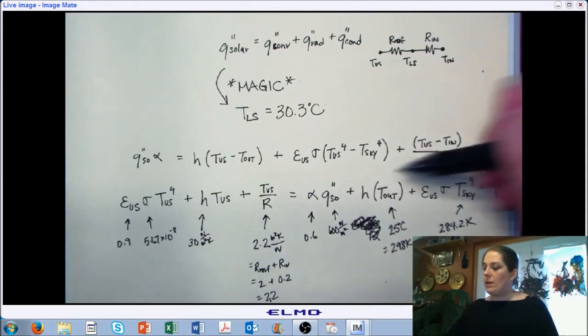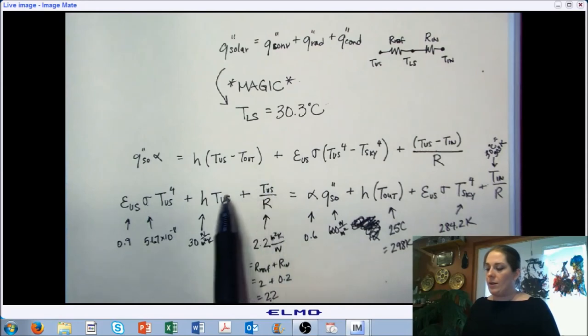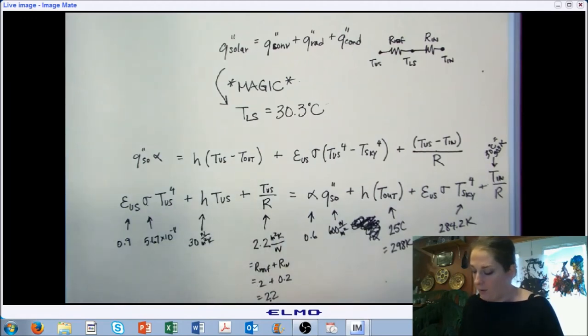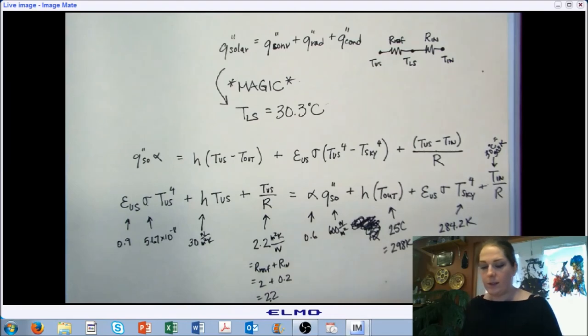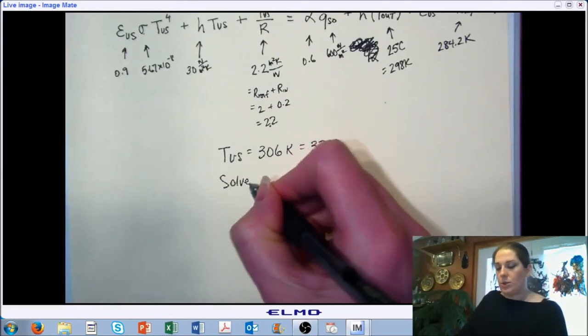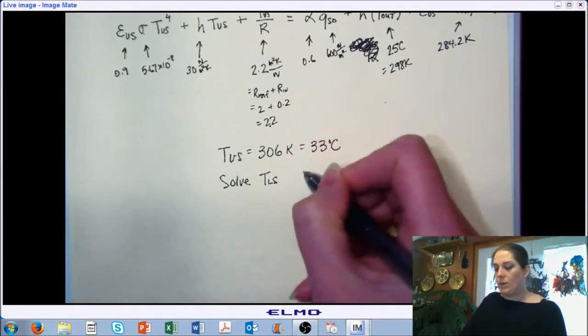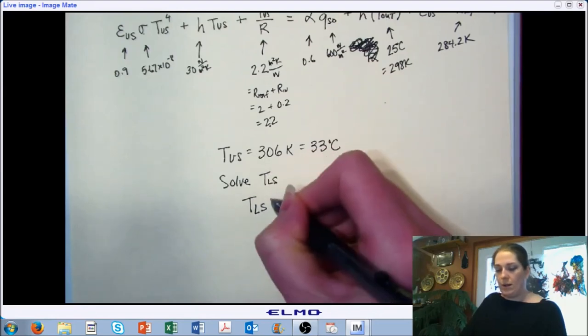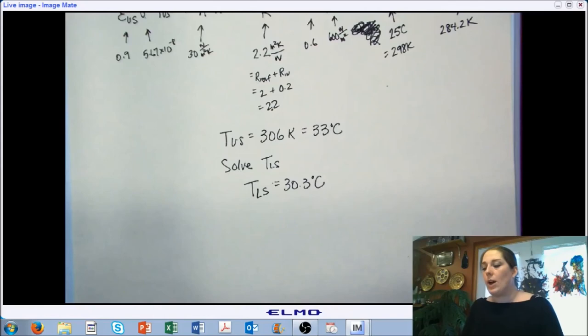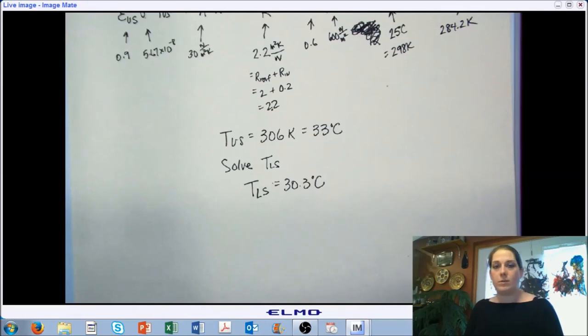Now everything on one side is a known value and our unknown is the upper surface temperature. Using an iterative process or computational software, the upper surface temperature should be 306 Kelvin or 33 degrees Celsius. From there, solving for the lower surface temperature using the same process as the last example gives 30.3 degrees Celsius. Those are our two examples on mixed-mode heat transfer, and this concludes the video lecture portion of our chapter on heat transmission through building structures.